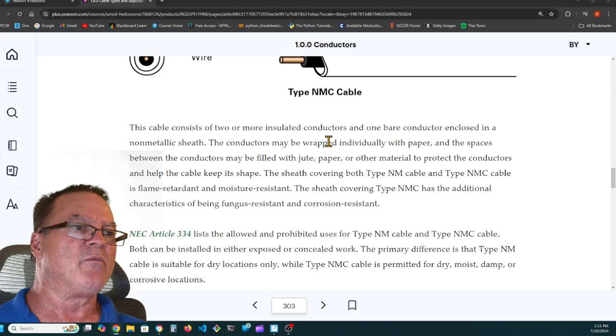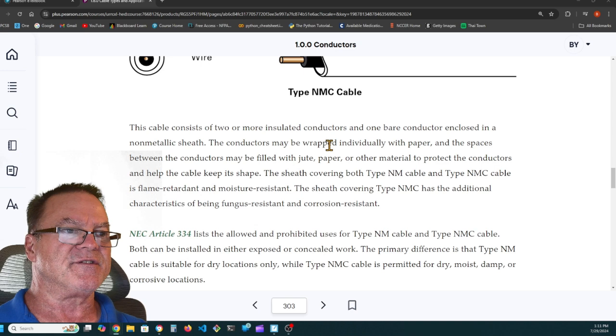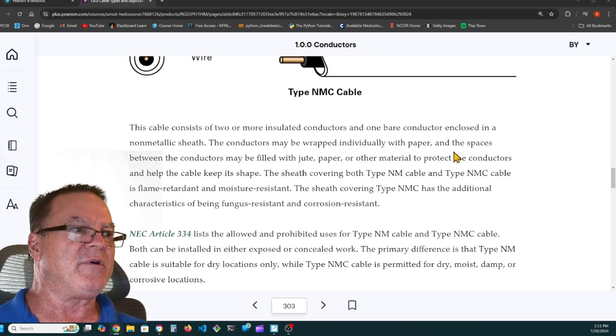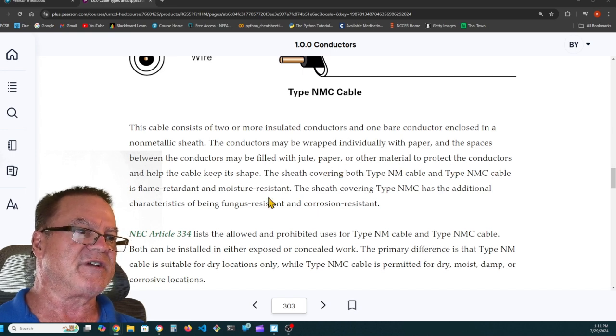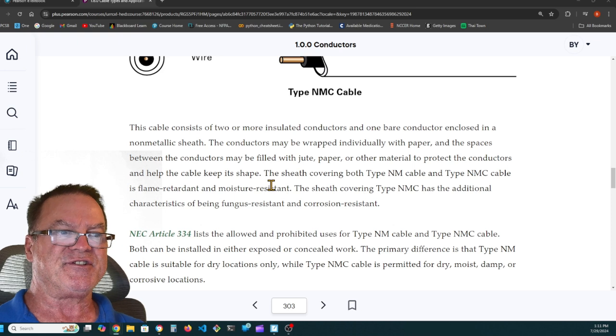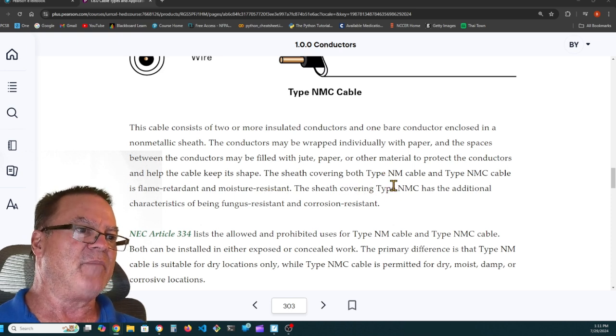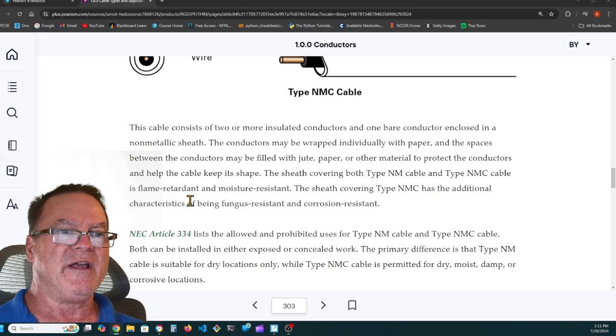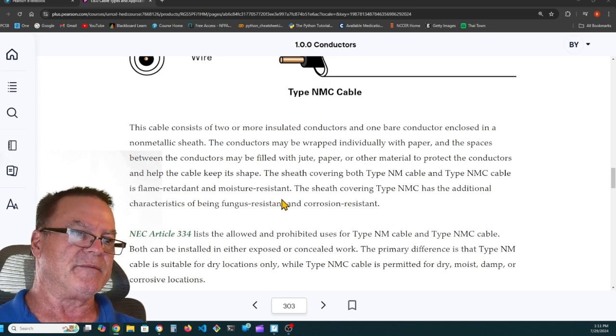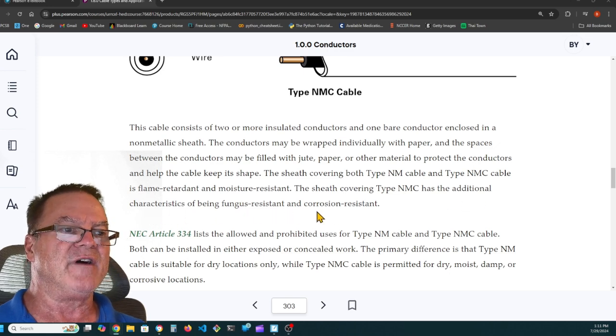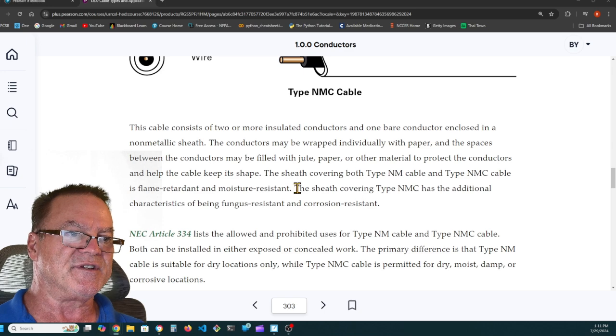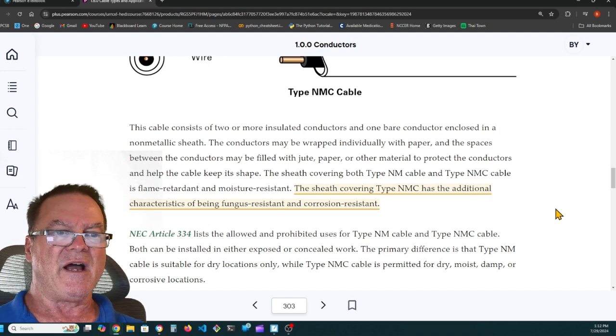This cable consists of two or more insulated conductors and one bare conductor enclosed in a non-metallic sheath. The conductors may be wrapped individually with paper, and the space between the conductors may be filled with jute, paper, or other material to protect the conductors and help the cable keep its shape. The sheath covering both type NM cable and NMC cable is flame retardant and moisture resistant. The sheath covering type NMC has the additional characteristics of being fungus resistant and corrosion resistant. All right, that is a highlight.